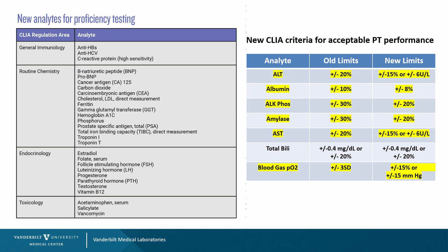Let's consider 2 different tests. Alkaline phosphatase. The old total allowable error limit of 30% is now tighter, 20%. So if we have a QC mean of 33.45, our peer group is running around 33.62, that calculates a bias of about 0.5%. Our CV, or imprecision, with this control at this level is 4.5%.